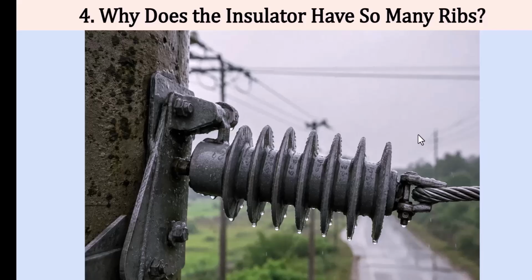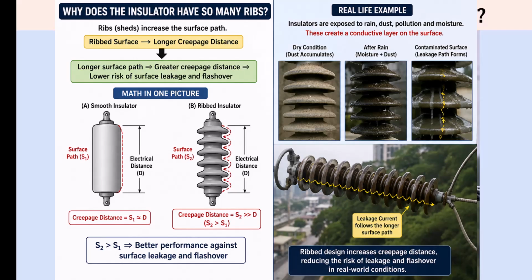The contaminated wet surface can support leakage current, so engineers want to make the surface path between the energized region and the grounded region longer. This surface path is associated with the creepage distance. Now the question arises, what is creepage distance? Creepage distance is the shortest distance measured along the surface of an insulating material between two conductive parts, such as an energized conductor and a grounded support. So remember the key idea: the longer the surface path, the greater the creepage distance, and the lower the risk of surface leakage and flashover.